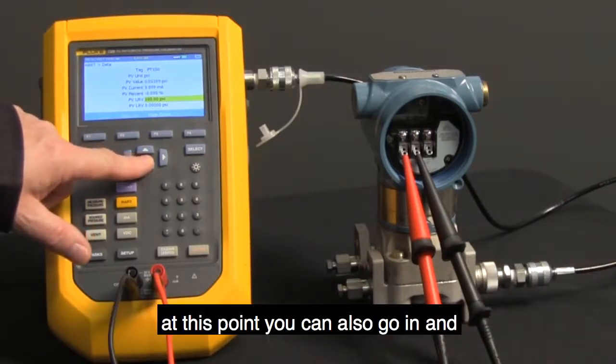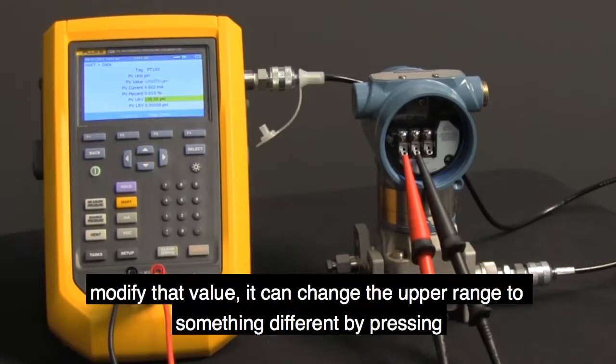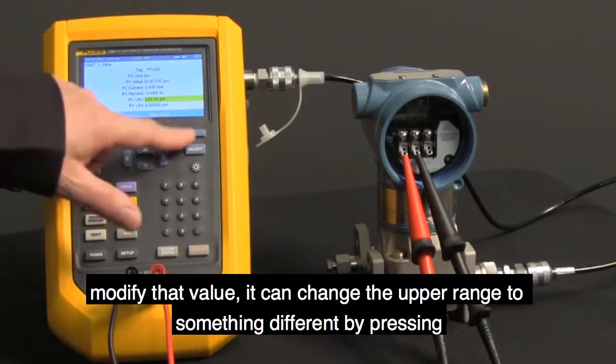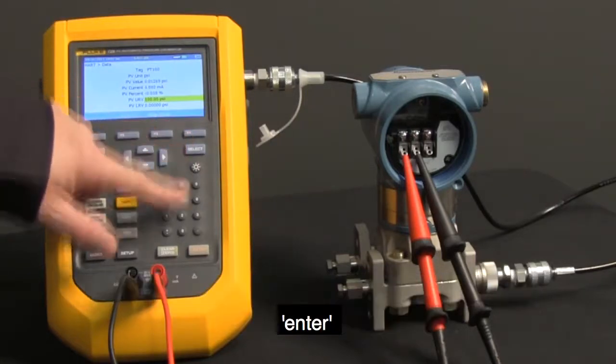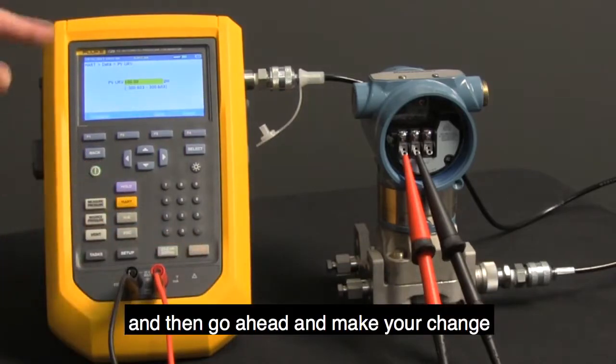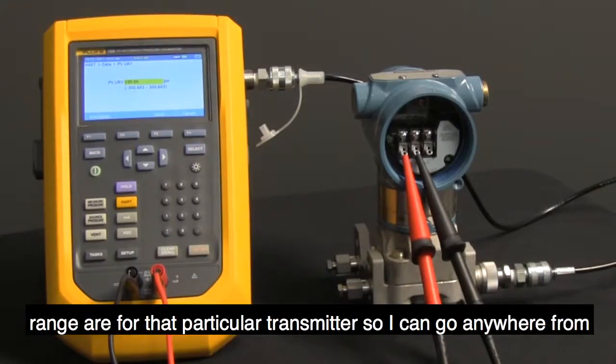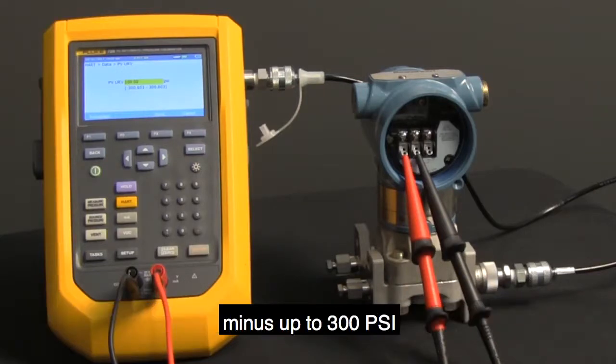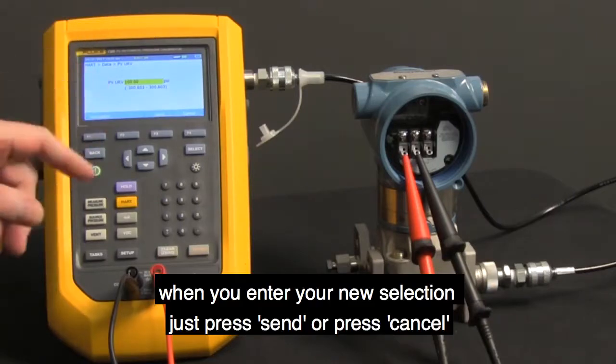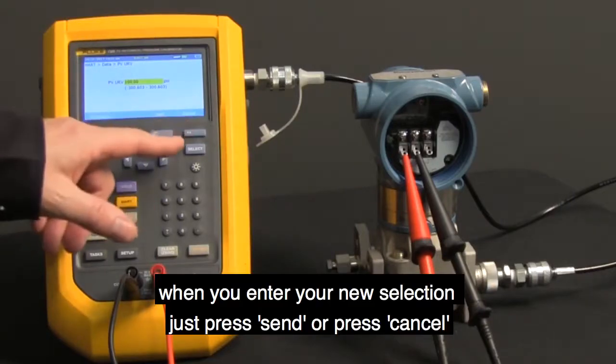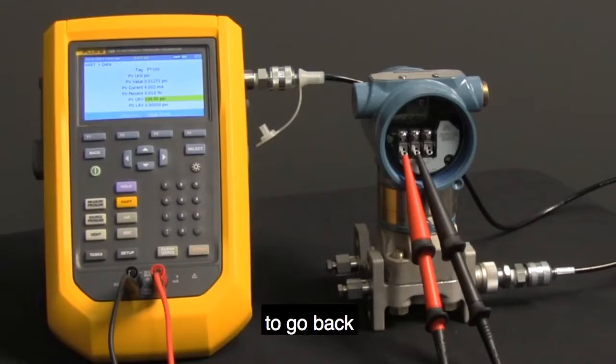At this point, you can also go in and modify that value. It can change the upper range to something different by pressing enter, and then go ahead and make your change. Notice, down below, it is showing you what the default values range are for that particular transmitter. So I could go anywhere from minus to up to 300 psi. When you enter your new selection, just press send or press cancel to go back.